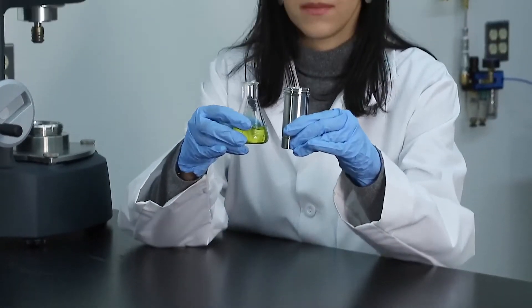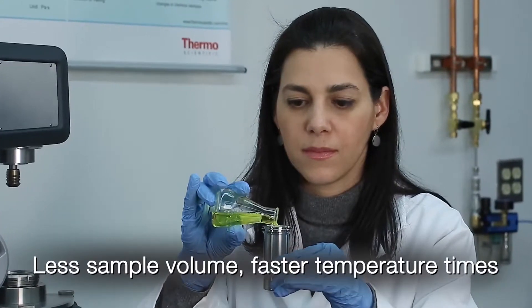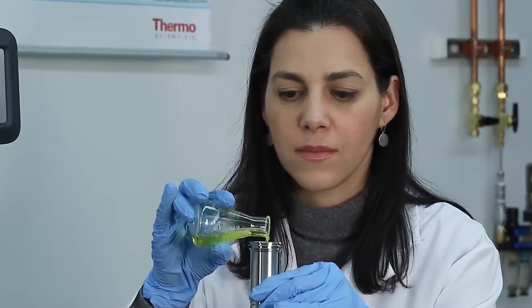Thanks to small-sized coaxial cylinders, you use less sample volume and have shorter temperature equilibrium times, minimizing your cost per measurement.